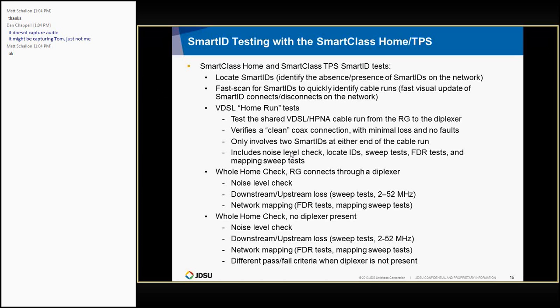That's basically a test that just runs out and finds which probes are on the network, or at least which probes it can see on the network. A fast scan is a variant of that. It keeps a continuous scan going and lets you quickly identify, when you pop cables on and off the network, which probes are being added or dropped, so that you can quickly identify cable runs.